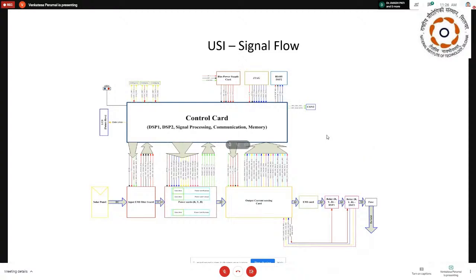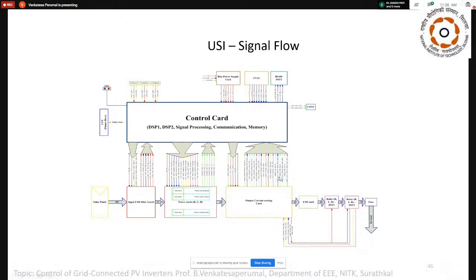So these are all the requirements coming from the standards. There's JTAG communication for the protocol, and here the voltage and current information from the grid side comes in. The control voltage requirement comes here, and the gating pulses come from here, with the sensed voltages and currents going to the other side. This is the DC current and DC voltage, represented in different colors so you can identify the R, Y, B phases and the DC side. It is also connected with a fan arrangement for cooling and other things.